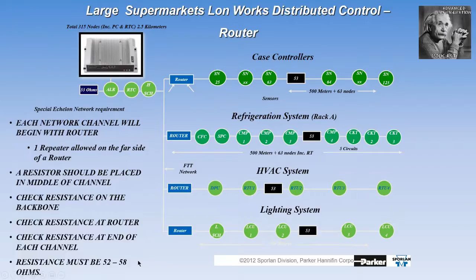Again, your resistor should always be at the middle. So at the very end, or the first thing on startup, what you'll want to do is get a multimeter out. You want it never lower than 52, never higher than 58, no matter where you put the multimeter - at the end, at the middle, out the router. Check it in 3 or 4 places, but it should be within 52 and 58 ohms wherever you check, every network segment.